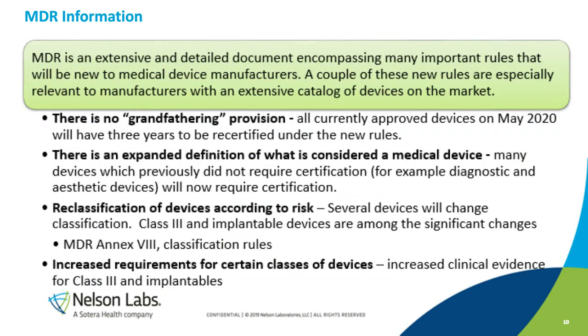Associated with all the information I have provided in the previous slide, what we need to remember the most is that there is a no grandfathering provision. All currently approved medical devices on 2020 will have 3 years to recertify under the new rules. There is also an expanded definition of what is considered a medical device. Many devices that did not previously require certification now will require certification.